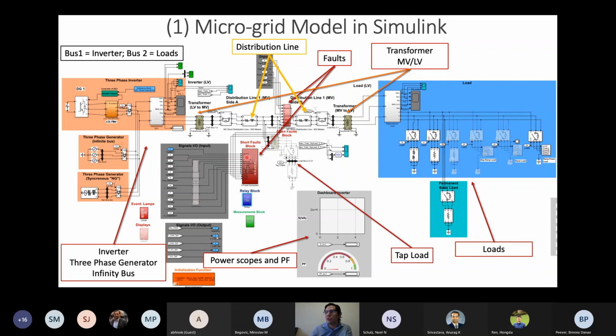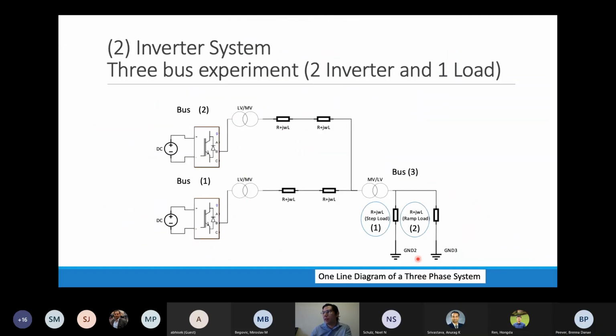So we are showing the short faults, which is the most critical. And then, this is the inverter model that has a 2-bus model. Compared to the previous one, which is the testing model, we need to also study the inverter, how it reflects into a microgrid that has more connected systems to each other. So we have 2 different buses, with 2 different inverters generating power in low voltage. This goes up to the distribution line, and they connect to a 3rd bus, which is basically having all the loads.